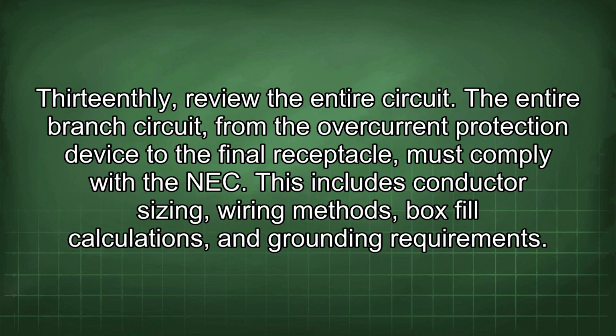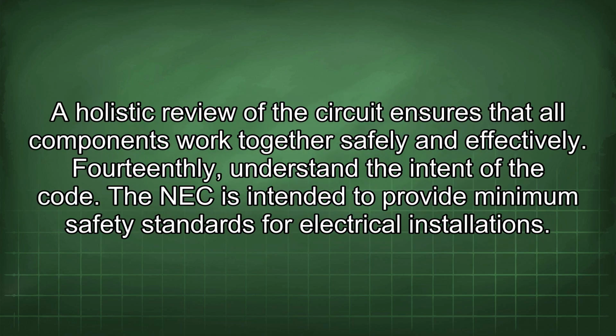13thly, review the entire circuit. The entire branch circuit, from the overcurrent protection device to the final receptacle, must comply with the NEC. This includes conductor sizing, wiring methods, box fill calculations, and grounding requirements. A holistic review of the circuit ensures that all components work together safely and effectively.